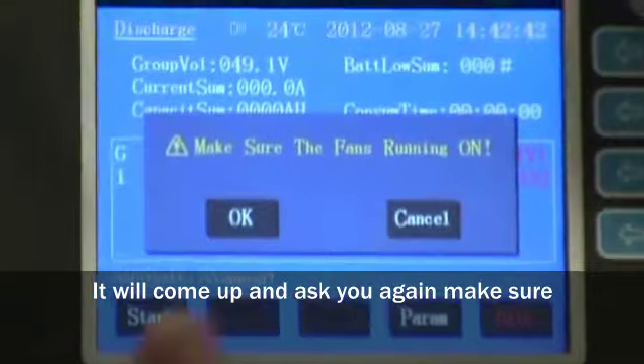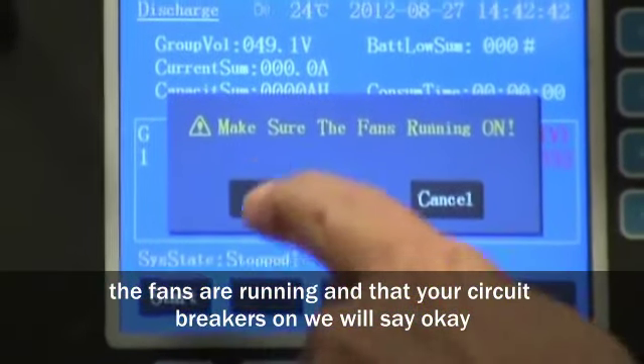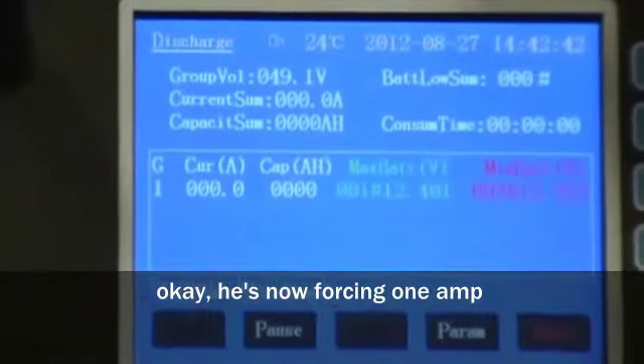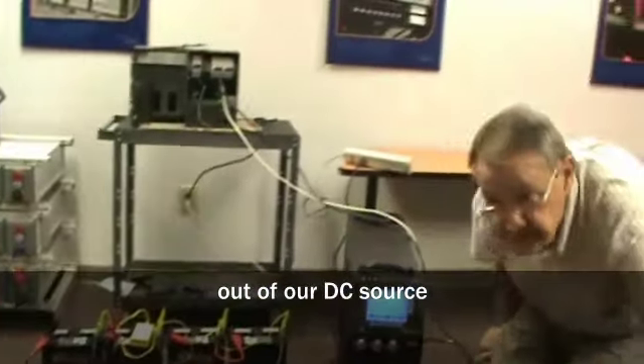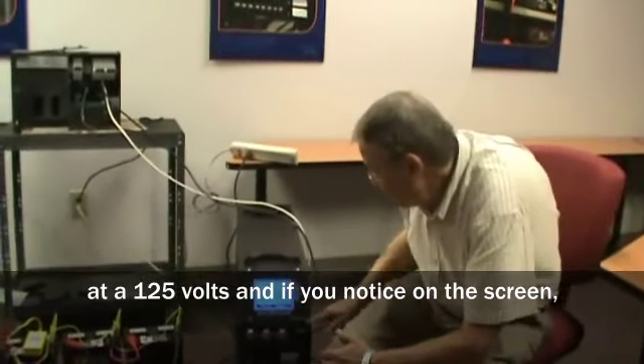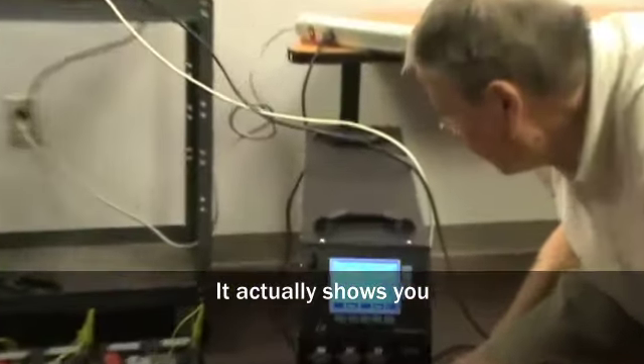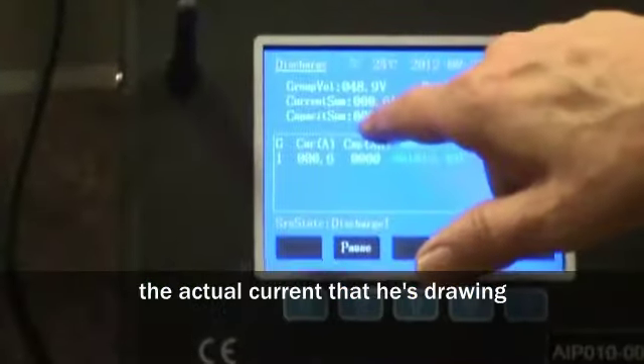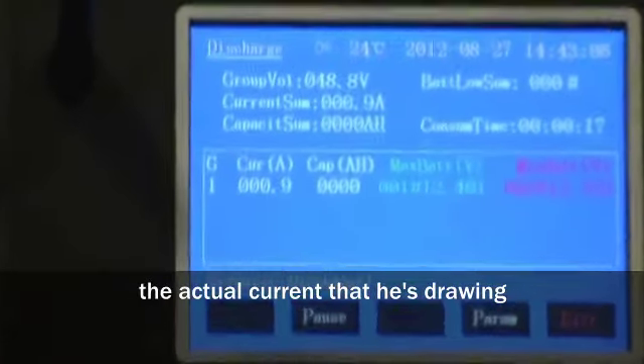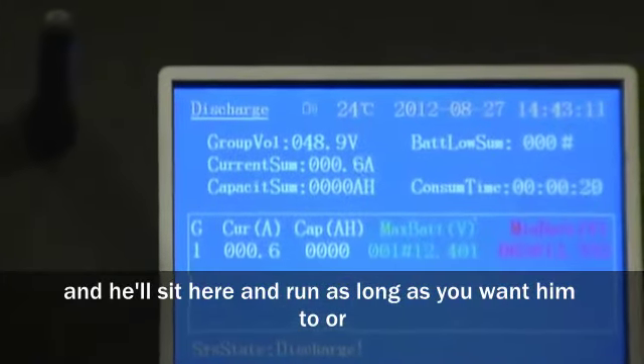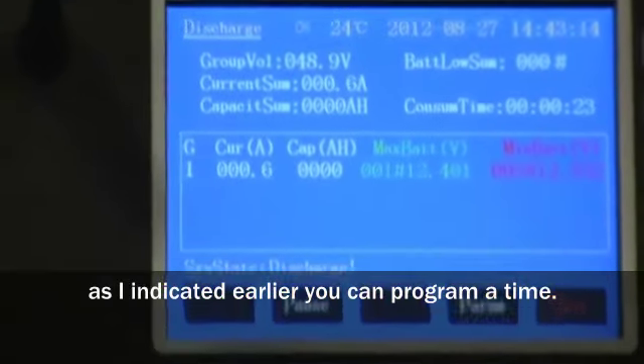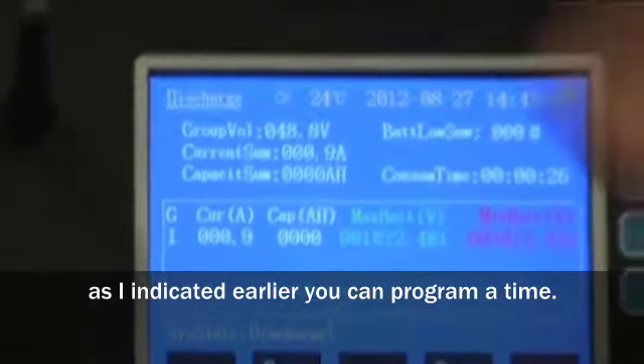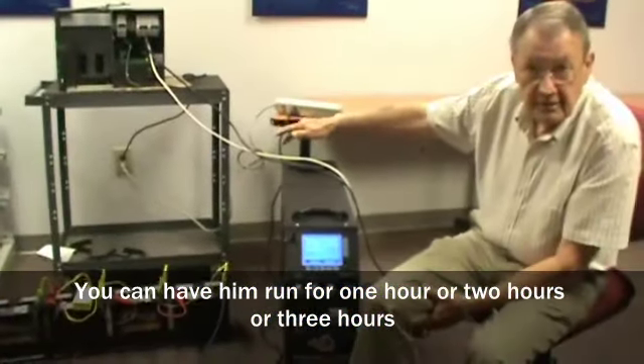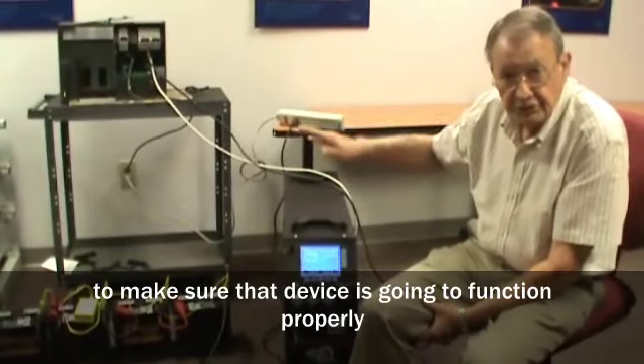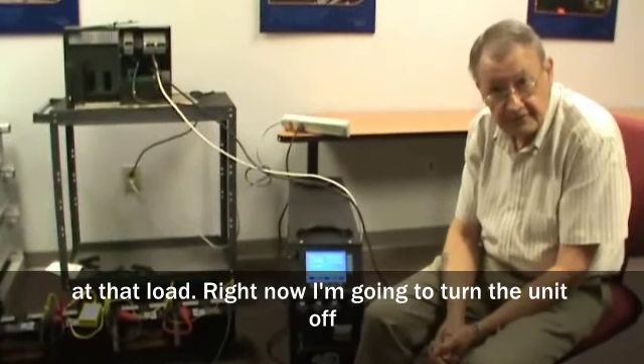It'll come up and ask you again to make sure the fans are running and the circuit breaker's on. We'll say okay, okay. And it's now forcing 1 amp out of our DC source at 125 volts. And if you'll notice on the screen, it's actually showing you the actual current that it's drawing. And it'll sit here and run as long as you want it to, or, as I indicated earlier, you can program a time. You can have it run for 1 hour, or 2 hours, or 3 hours, to make sure that that device is going to function properly at that load.